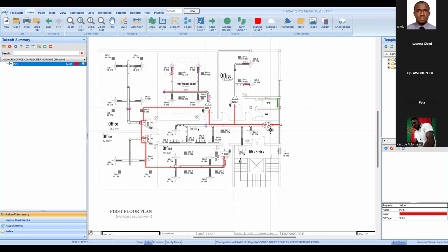Now, if it is 1 core by 4 mm cable, it shows that you have 4 runs. What do I mean by 4 runs? You use 4 numbers of cables. We've already calculated 6 meters at the height and 42 meters internally, making 48. Let's now allow for termination. Termination means at every fan coil unit, 1 meter will be dropping based on our headroom. Now we have 6 meters, we have 1 meter, and we have 6 numbers of fan coil units. That's 6 meters plus 42 making 48. 48 plus 6 making 54 meters.